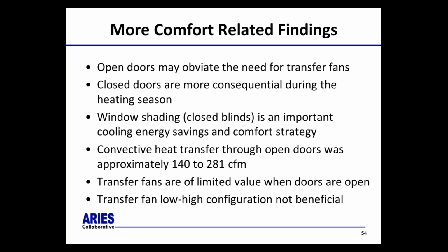A couple other findings: open doors may obviate the need for transfer fans. This stands to reason — when you close a door, you're basically down to your fans for air movement, a prisoner of your fans. When doors are open, there's much more mixing between spaces, and much less likely horizontal stratification of temperature. So if you can keep your doors open all the time, you're home free. Closed doors, which is the reality in the world, are more consequential during the heating season, at least in Alabama.